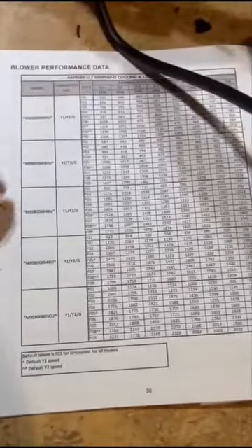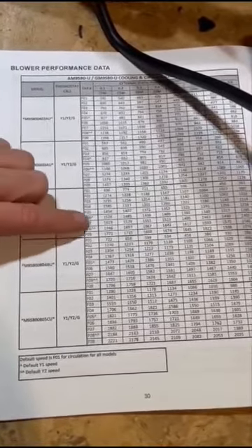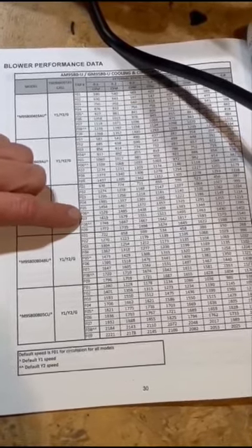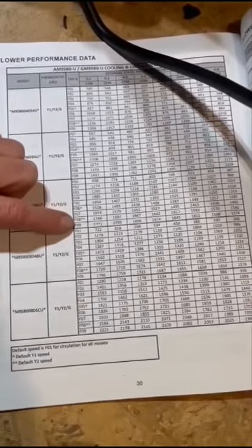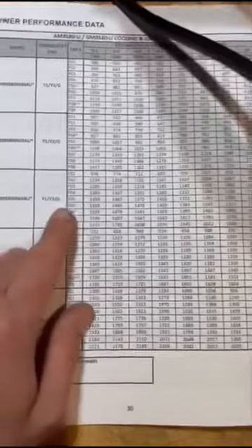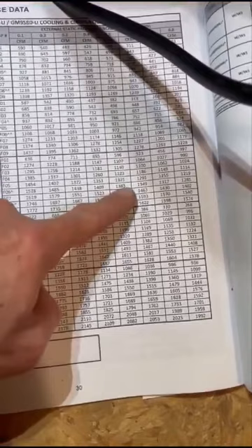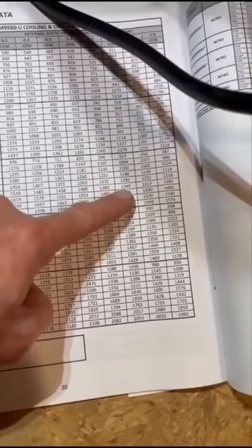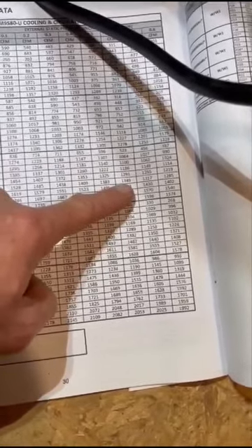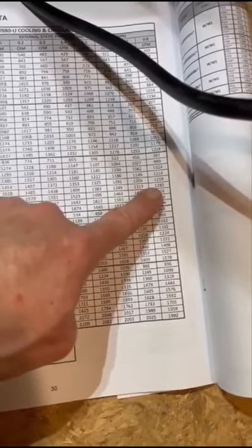Okay, so the unit we have is the GM9S 60,000 BTU 4-ton. And the factory speed for AC1, because this is the cooling chart, is F06. And for AC2, if it was a 2-stage, it will be 08. Now, since we did the airflow class, we know that most of these units are gonna run around 0.6 to 0.8. So if we put it on 0.6, it should be around 3.5 ton capacity. If we put it on 0.8, it's gonna be 3 ton capacity.